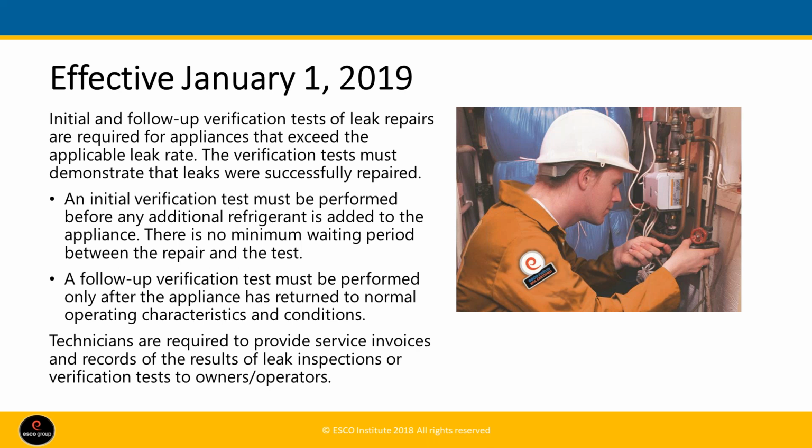Also, there is no waiting period between performing a leak repair and retesting the system for a leak. Only after verifying the system is leak-free can the appliance be returned to normal operation conditions. And then that's when the follow-up verification test can be performed. So they want it performed under normal operating conditions.